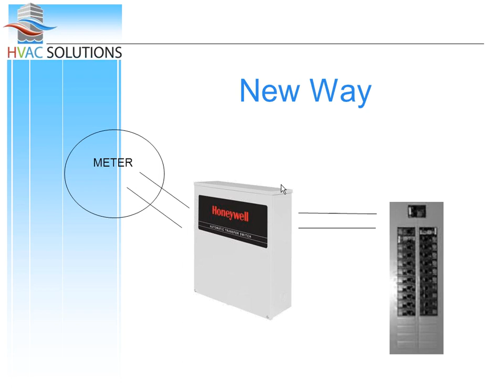So how does all this work? Well, if I was to run through what is going on here, this circuit board is inside of the transfer switch. If I run through a sequence of events, we lose power, the generator kicks on. We send power through the transfer switch, and the first thing that happens is that we give power to the circuit breaker panel. And when I say circuit breaker panel, what I'm really talking about is the 115s, the 115 volt circuits on that panel. So in a house, what are the 115 volt circuits? Well, it's the outlets, it's the lights, it's the refrigerator, it's the TV, it's the sump pump, even the garage door.